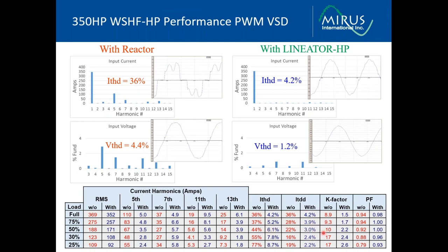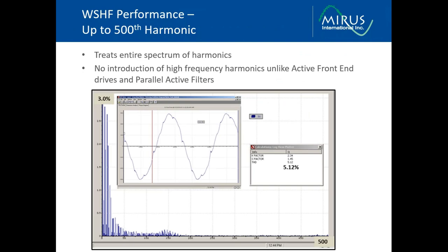So we can see that with this application, this filter is well below 5% over the entire operating range. You can see the reduction in K factor, so there's no longer a requirement for upstream K-rated transformers. And the improvement in power factor, you can see we're virtually unity power factor across the full spectrum. And unlike active solutions, such as active front end and parallel active filters, the wide spectrum harmonic filter does not introduce any higher order harmonics.